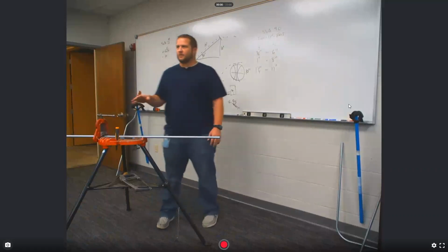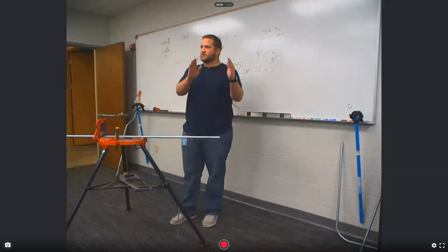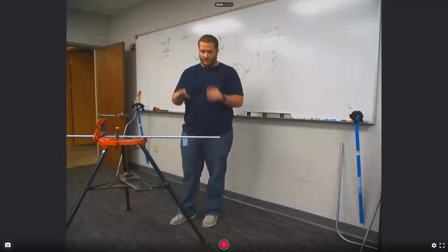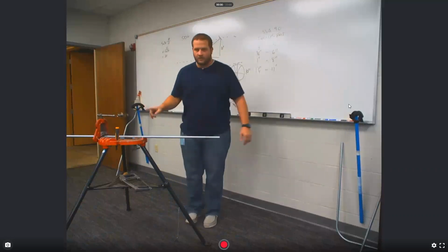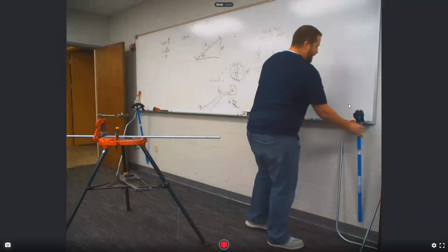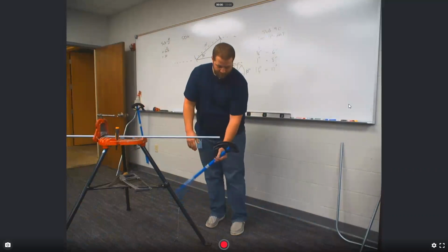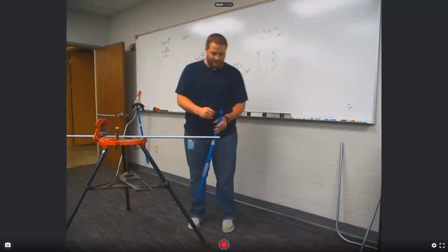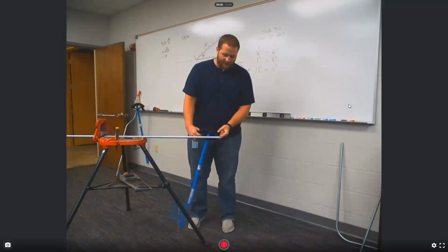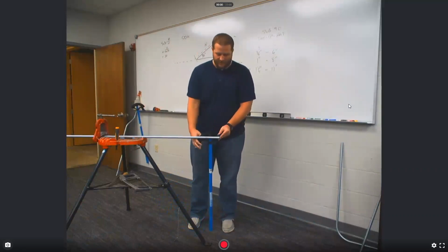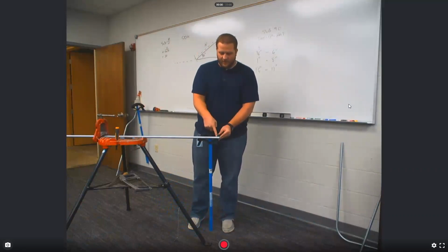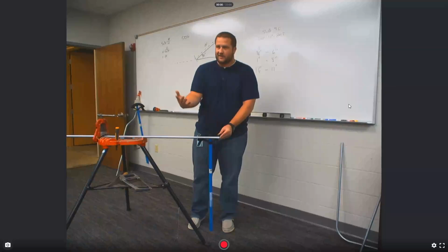Not take out. What you're thinking about is shrink, and eventually we will get to that because the pipe, as you bend, will start to shrink back. But if I put the bender right on the end of the pipe, so my hook is right on the end, my arrow is not on the end of the pipe, right? My arrow is right there, and it's like 3/4 of an inch or something.